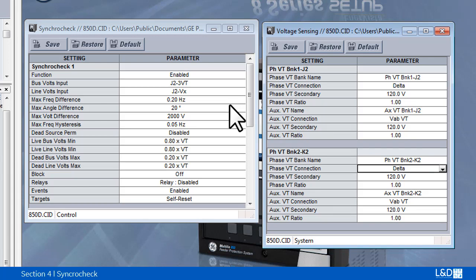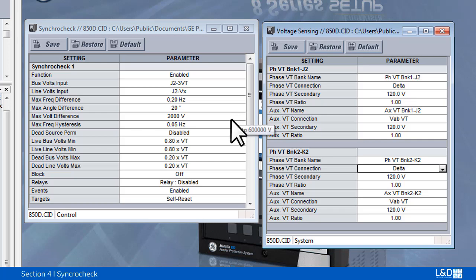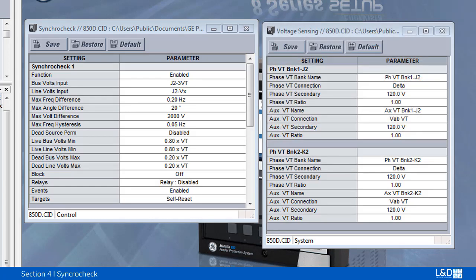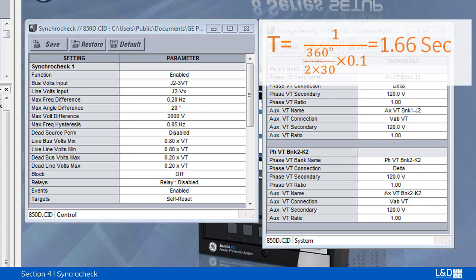The time during which the two voltages remain within the admissible angle difference is determined by the setting of the phase angle difference delta phi and frequency difference delta f. When delta phi is 30 degrees and delta f is 0.1 hertz, then the calculated time will be 1.66 seconds.